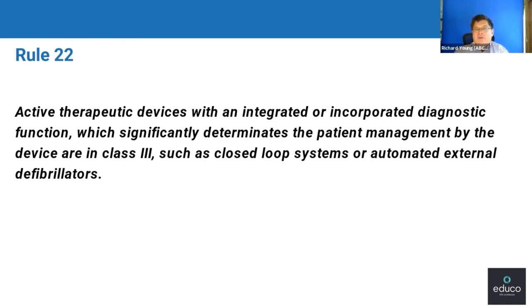I hope I've given you just a really brief overview of this today. It's really important you sit down with your designers and your regulatory professionals to go through these really systematically and document your thinking and the reason you've chosen your classification for your product very clearly. And I hope I've also demonstrated it's important to look all the way through here and really determine whether one or more rules can apply to your product based on its intended use and your design there.